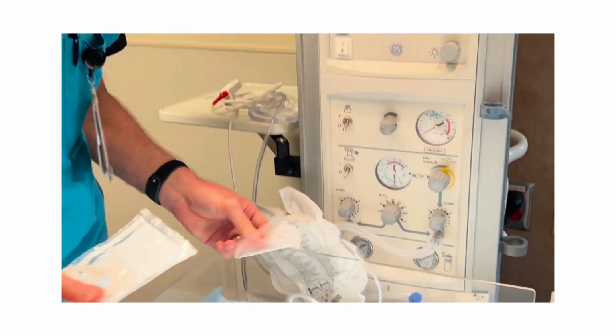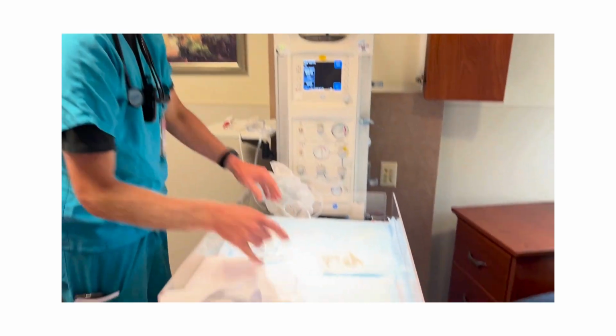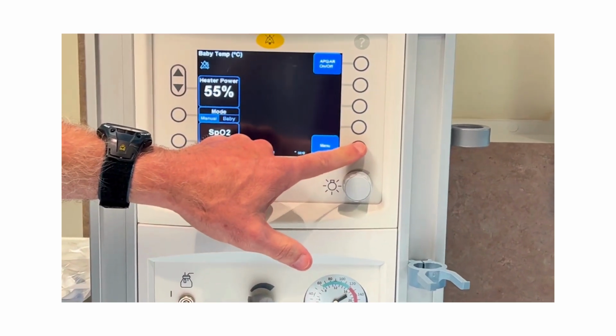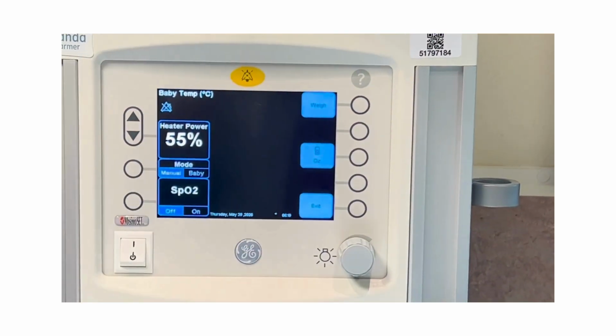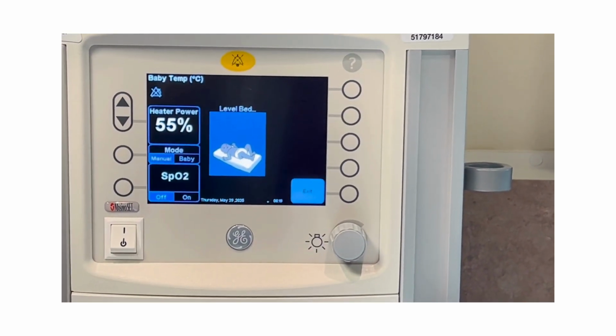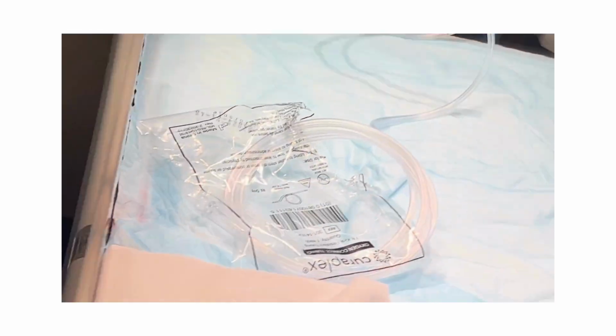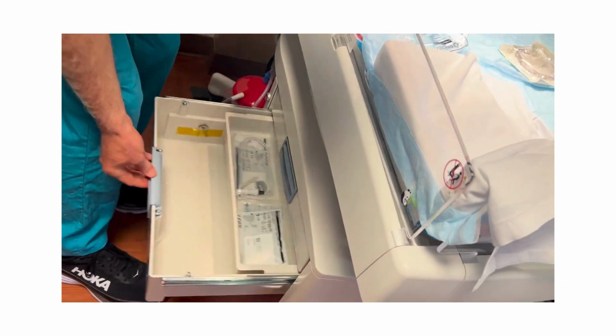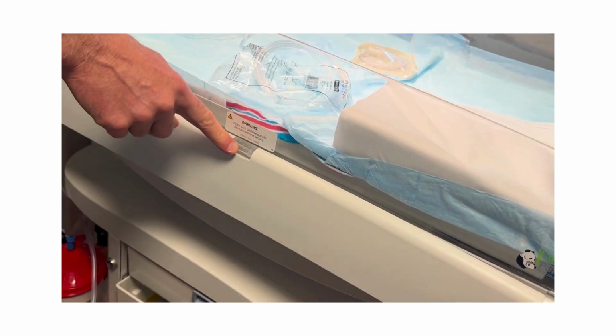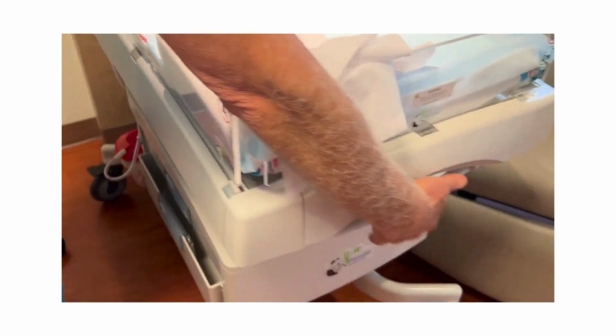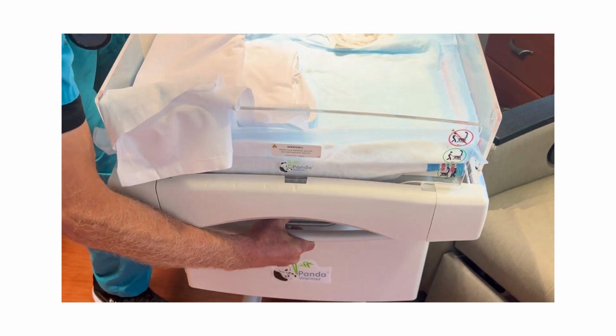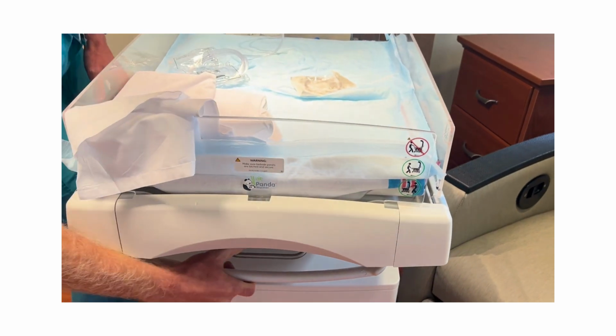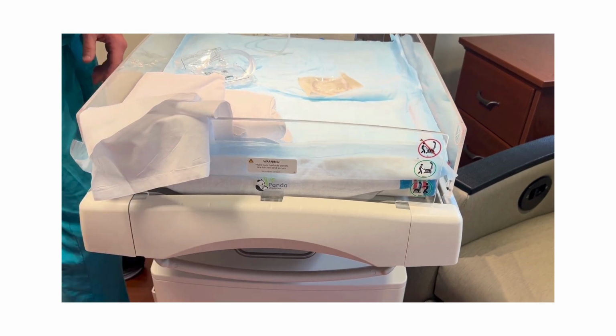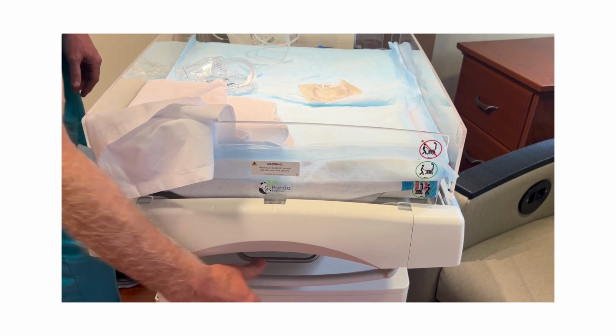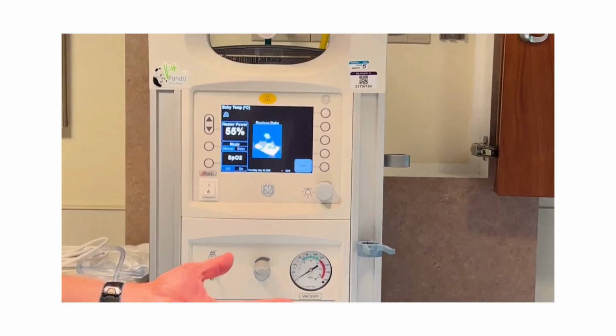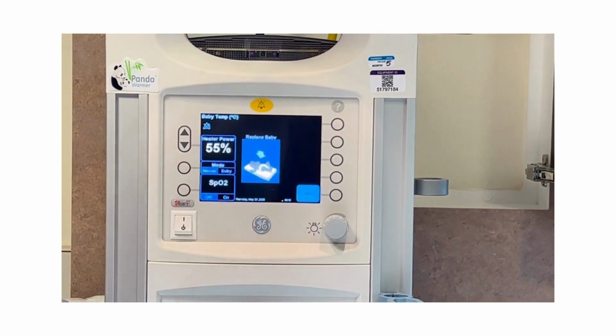And it'll weigh the baby. I'm sure you're probably familiar with these. It has a scale built in, and if you need to weigh your baby up here, you can hit menu, and you can go to scale, and then you can click weigh, and it'll ask you to make sure the bed is level. To make sure the bed is level, there's a little bubble on the side of these right here, and you need to adjust it, up or down with this little handle right in here. You just squeeze the handle, it can tilt the bed down or tilt the bed up, and you want to keep it to where the bubble's right in the middle so you can get the most accurate weight. And then it'll tell you to lift the baby. It'll lift the baby until it says replace the baby, and then it's taring the bed, and then you replace the baby and it'll weigh. So that's how you weigh.